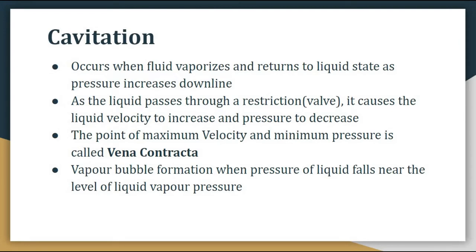Now let us talk about cavitation. Cavitation occurs when fluid vaporizes and returns to liquid state as pressure increases downstream. In flashing, the fluid vaporizes and stays in vapor state. In cavitation, it vaporizes but then returns to liquid state because pressure increases, and the damage that occurs is called cavitation. As the liquid passes through a restriction, it causes liquid velocity to increase and pressure to decrease. For example, if you have a nozzle and you hold its tip, you will see the velocity of the liquid coming through it changes.